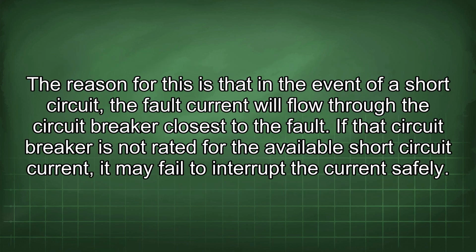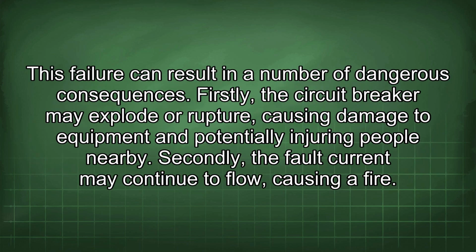The reason for this is that in the event of a short circuit, the fault current will flow through the circuit breaker closest to the fault. If that circuit breaker is not rated for the available short circuit current, it may fail to interrupt the current safely. This failure can result in a number of dangerous consequences.